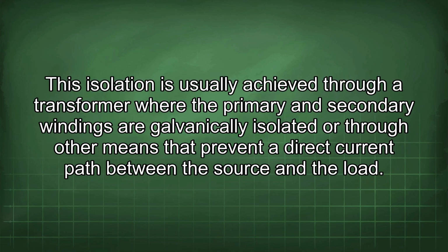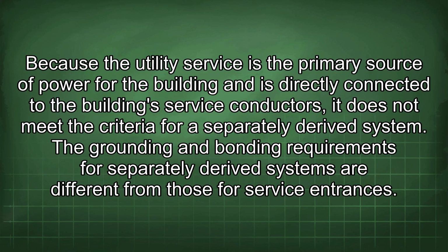This isolation is usually achieved through a transformer where the primary and secondary windings are galvanically isolated, or through other means that prevent a direct current path between the source and the load. Because the utility service is the primary source of power for the building and is directly connected to the building service conductors, it does not meet the criteria for a separately derived system.